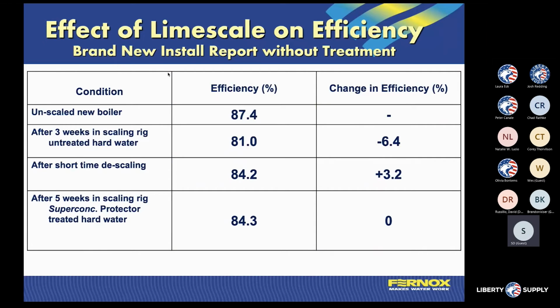So the biggest problem with water quality overall is if I start with a brand new system and I flush it out and do all the right things and install that system, and I don't inhibit the fluid inside of that heating or cooling system, we're going to rapidly start to lose efficiency. So this is a case study that was done in a 3-week period where we put a brand new standard efficiency boiler in. After 3 weeks, we went down from 87.4% efficiency right down to 81. And then the thought would be, well, I go and clean it and then everything will come back to normal. Well, that doesn't always happen correctly. So in this case, after cleaning and descaling and trying to do the best job they could, they got it back from 81 up to 84. So there's still a 3% efficiency loss at the fuel stack or the fuel bill from that standpoint.